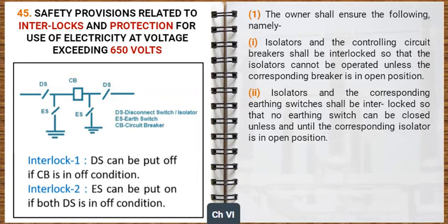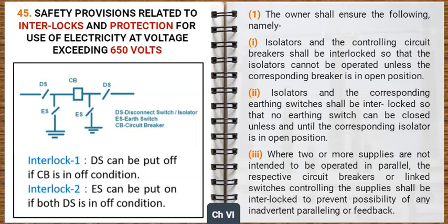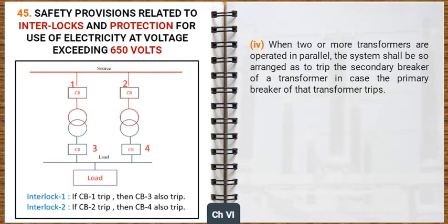Where 2 or more supplies are not intended to be operated in parallel, the respective circuit breakers or linked switches controlling the supplies shall be interlocked to prevent possibility of any inadvertent paralleling or feedback. When 2 or more transformers are operated in parallel, the system shall be so arranged as to trip the secondary breaker of a transformer in case the primary breaker of that transformer trips.